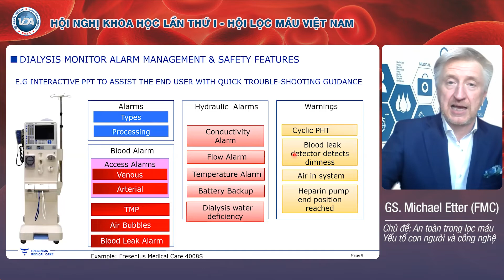So everybody knows that once the venous needle dislodges from the patient's access and the machine doesn't stop, it pumps the patient's blood right into the environment. It's a process of exsanguination, and the patient will die if you don't stop it. Therefore, the venous pressure alarm is, I think, one of the most important alarms that you need to set on your machine. If you don't set the venous pressure alarms properly, your main control for venous needle dislodgement is gone.